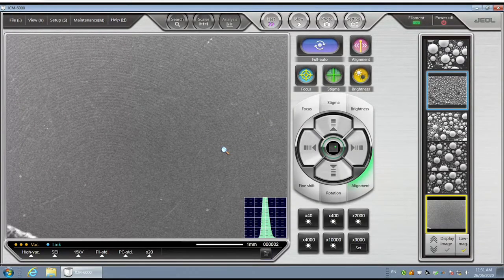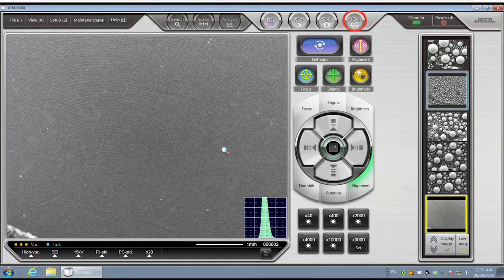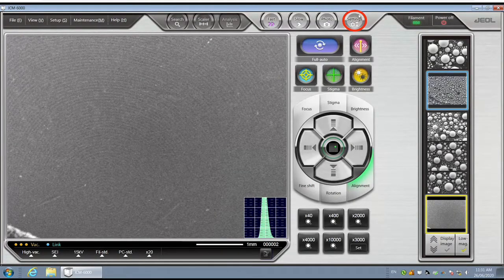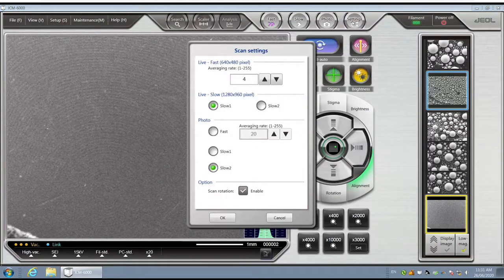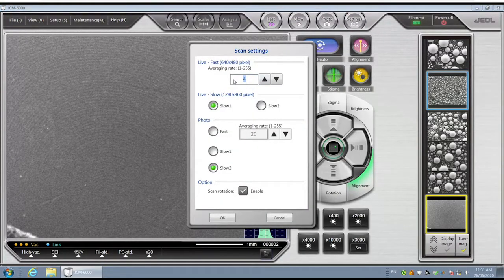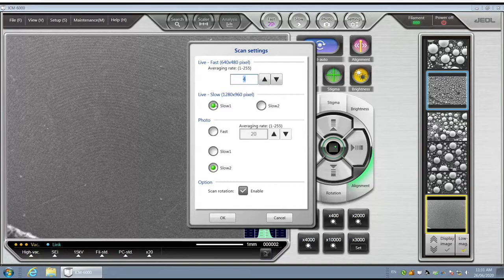Go to the Scan Settings options at the top right and make sure you have the correct settings for your sample. We recommend the averaging rate is set to 4, the live slow is set to slow 1, and the photo is set to slow 2.